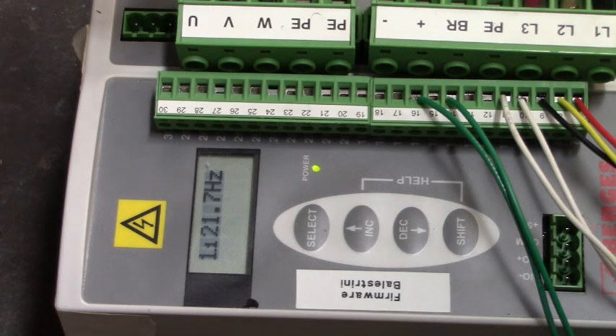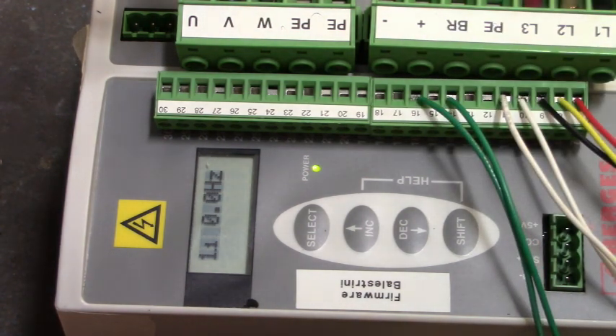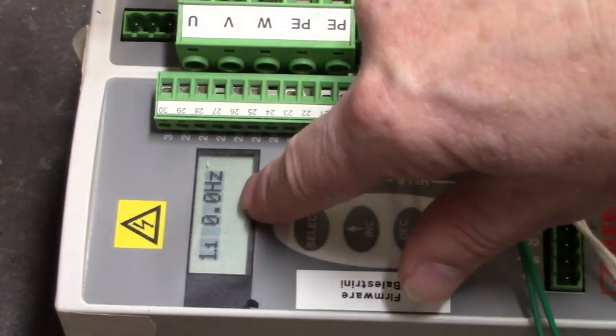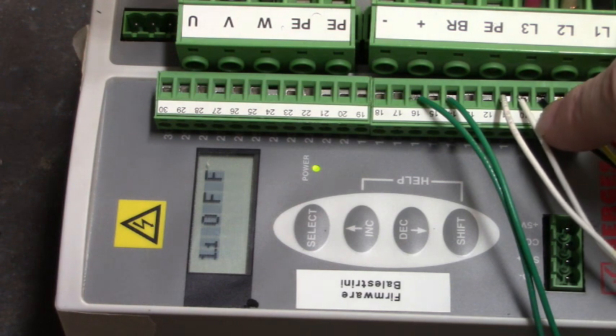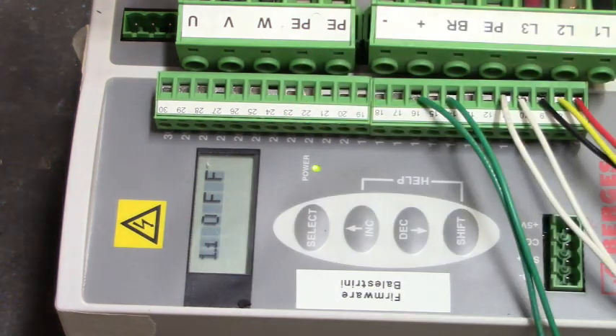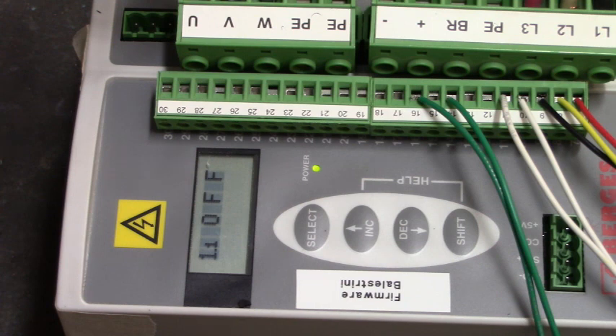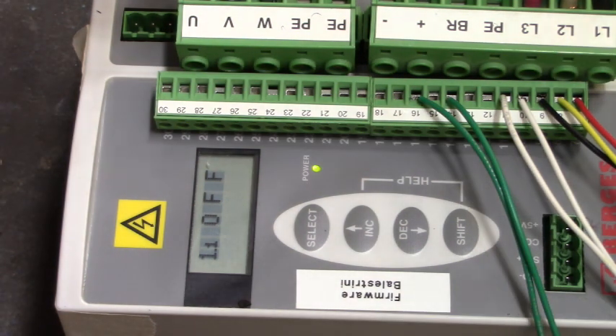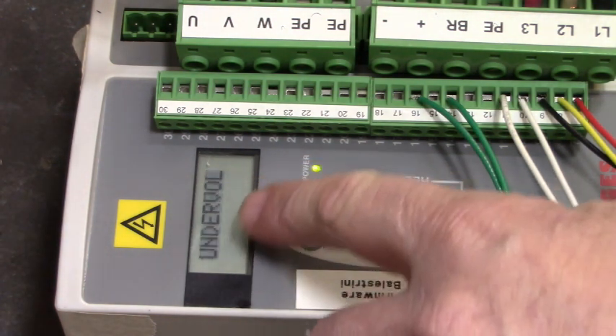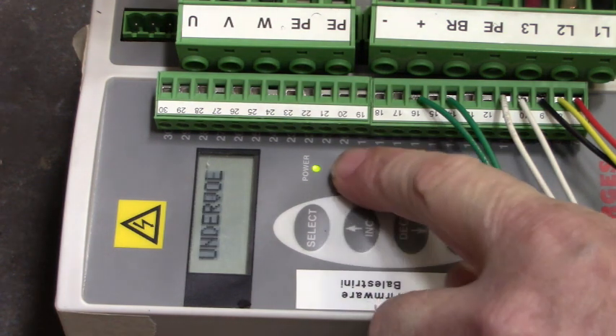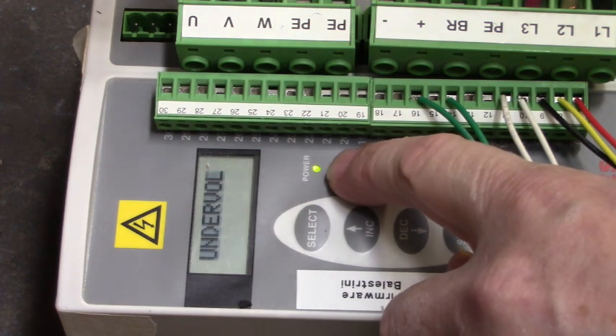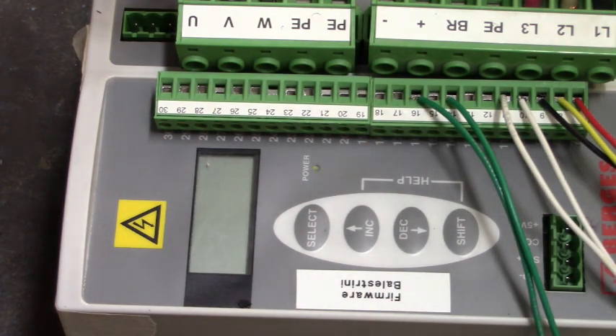I'm going to turn the drive off, open up the run forward switch on terminals 14 and 16. We've gone to 0.0 hertz. I'm going to open up the enable on terminals 10 and 11, and we're back to off. Remove the 380 volts AC three phase from L1, L2, and L3. Now you can see it says undervolt. In a little bit, the power LED will start blinking as the bus capacitors start to die off. There we go. Fully powered down. Takes a little bit.